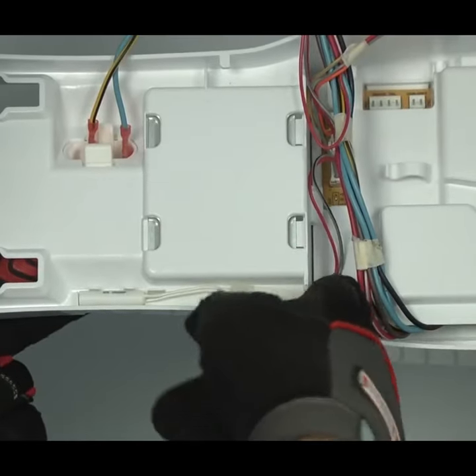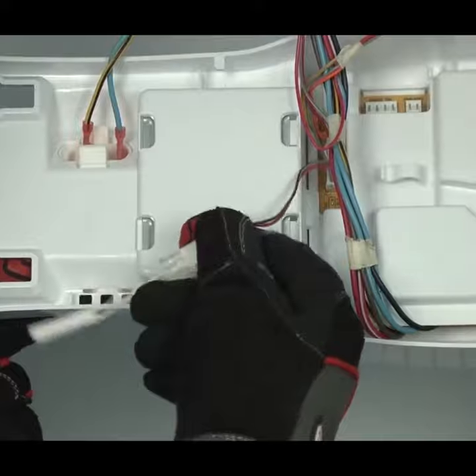Examine the thermistor's wire harness for damage or loose connections. If the wire harness looks okay, let's check the resistance of the thermistor using a multimeter.